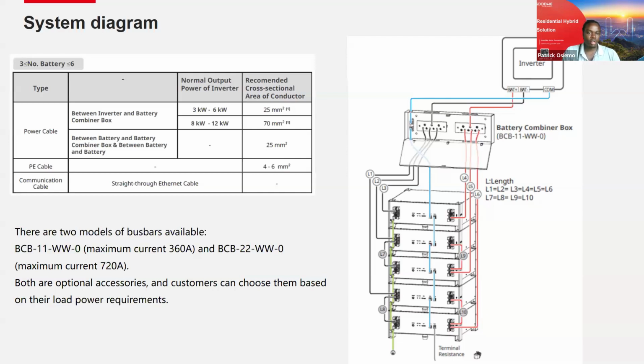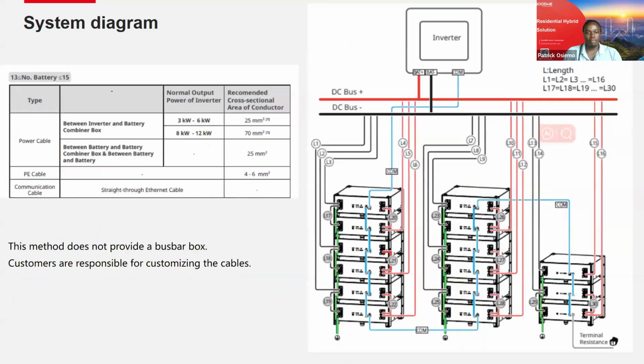It's actually a good technical advice or feature to install your batteries in this sense. So our battery combiner box has 2 versions. We have the BCB11, which can handle a maximum of 360 amps, and BCB22, which can handle a maximum of 720 amps. And if you're scaling your system or your storage to higher levels, let's say 15 pieces, 30 pieces of Lynx A, then you can use a third party, make your own bus bar, and connect the DC cables to this bus bar. The communication will be looping from the first battery all the way to the last with the terminal resistor on the last battery.